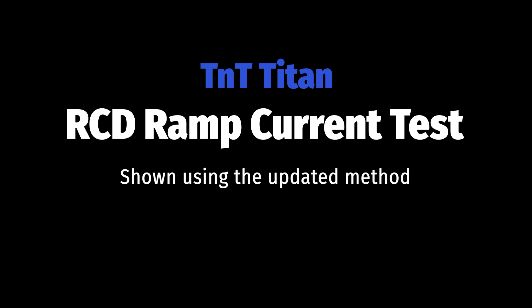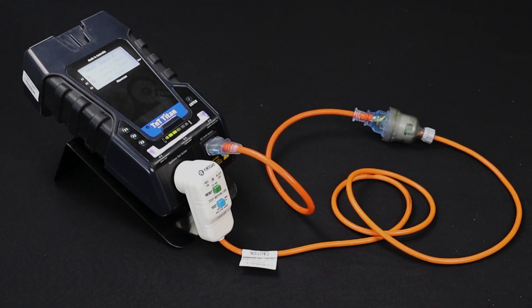Let's move on to testing portable RCDs. We'll start with a ramp current test. First, we conduct our visual inspection and determine what type of RCD we have. This example is a type 2 portable RCD. In this example, we are using the updated test method. If in doubt, consult your TnT Titan user manual.